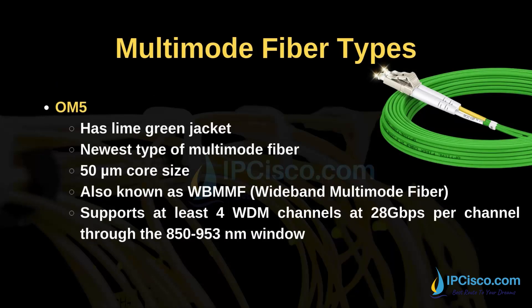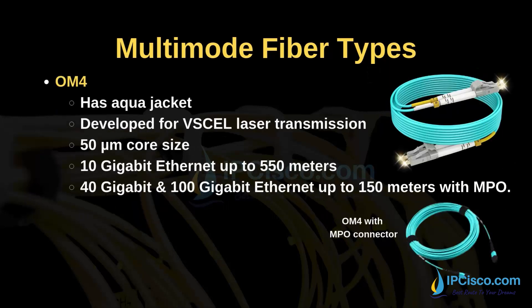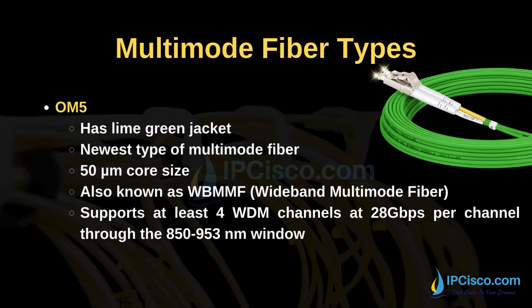Yes, this is the answer to our question at the beginning. OM5 is the latest multimode fiber technology today. The jacket color is changing again — OM5 has a lime green jacket. It has a 50 micrometer core size. OM5 is also known as WBMMF, wideband multimode fiber. It supports at least 4 WDM channels at 28 gigabits per second per channel through the 850 to 953 nanometer window.